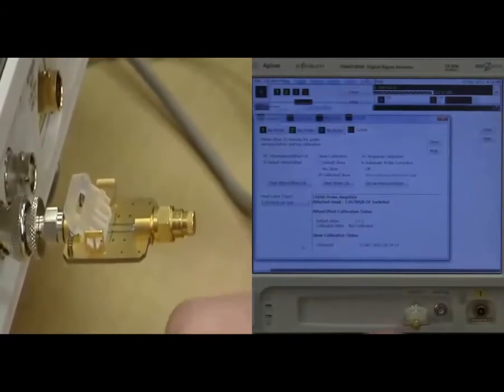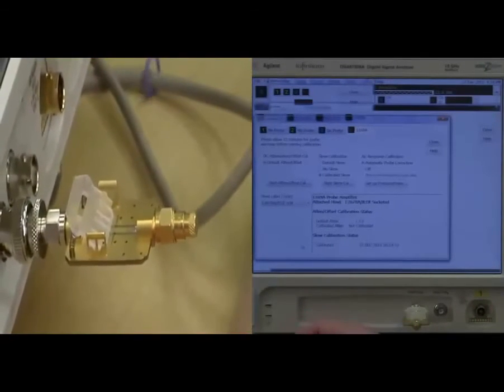It's also worth noting that we can also, for just the offset and DC gain, just touch the positive sides of the probe compensation lug. However, this is no good for doing the skew calibration. Thank you for your attention.